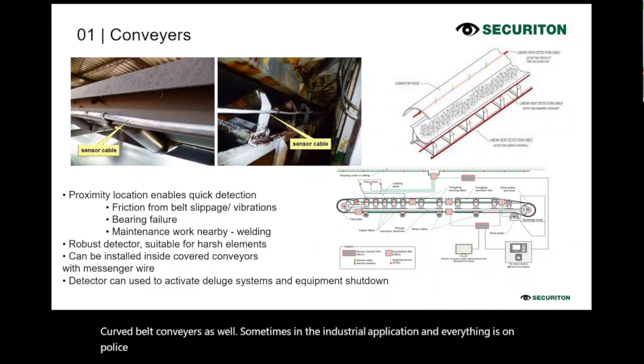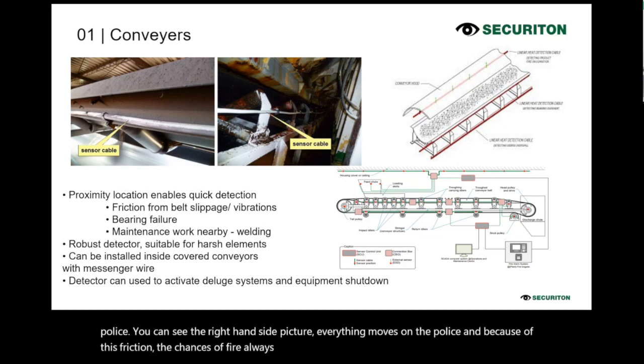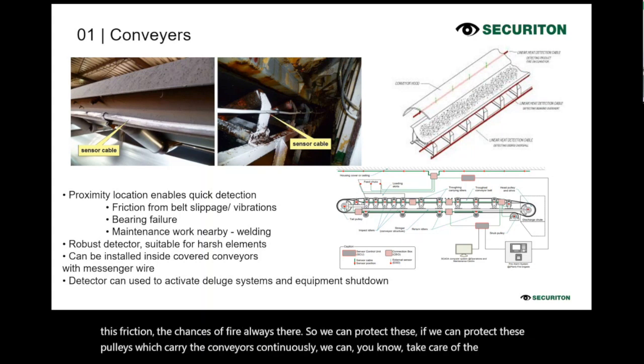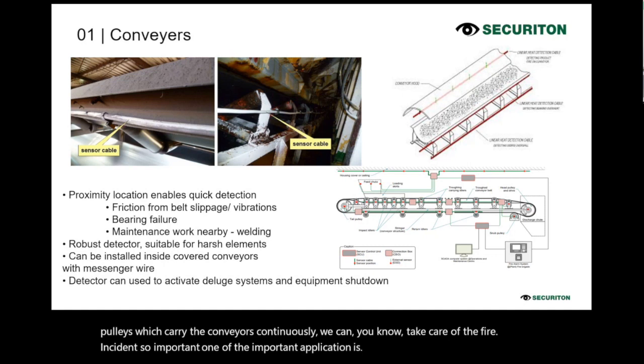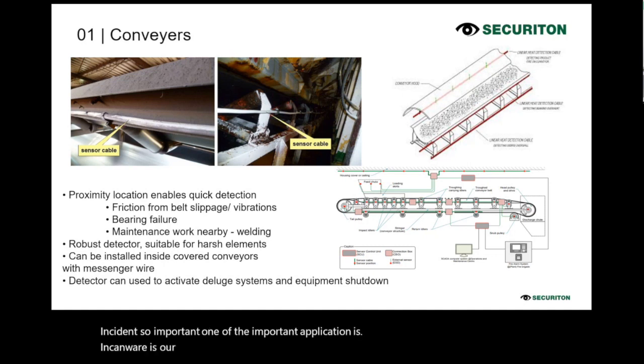Everything is on pulleys; you can see in the right hand side picture that everything moves on the pulleys, and because of this friction, the chances of fire are always there. So if we can protect these pulleys which carry the conveyors continuously, we can take care of the fire incident. One of the important applications on conveyors is our solution, the linear heat sensor. You also have steel cables on the conveyor, and sometimes these steel cables also create fire chances.